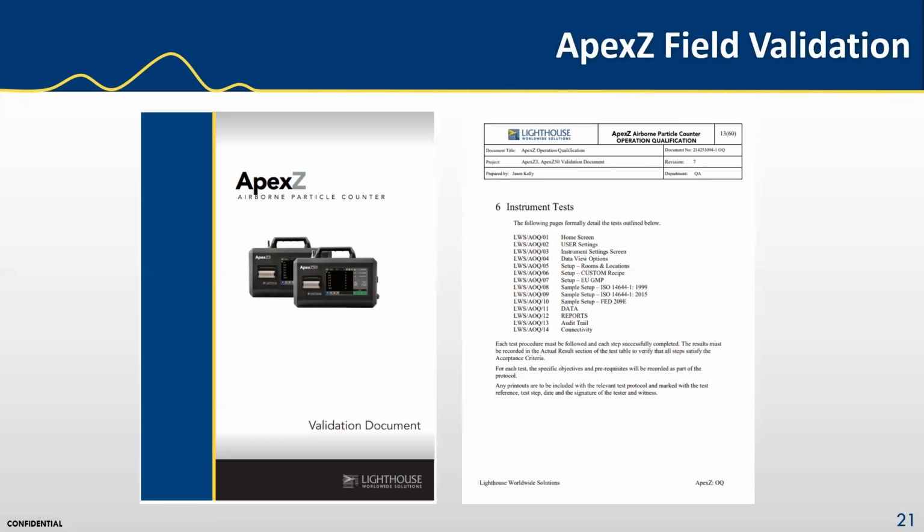I need to stress that there are some 21 CFR Part 11 requirements that the end user must complete on their end, which are outside of the vendor's capabilities and must be part of the end user's validation, which should be addressed through their quality system and use of SOPs as well.